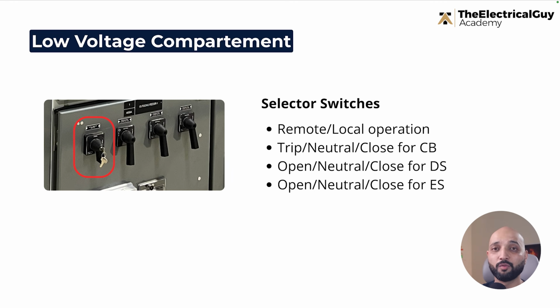Or else, let's say you don't want a remote command, you are standing right in front of the panel and you need to close the circuit breaker. In that case you turn this switch towards local operation. The moment you turn it, all the wiring will allow you to operate the circuit breaker using the local contacts. If it's on the remote side, you won't be able to do anything here. The circuit breaker will not trip. If you want to locally trip the breaker, you must put the handle on the local selection. Then only it will work. So this is also a kind of interlock, and remote/local is commonly seen.